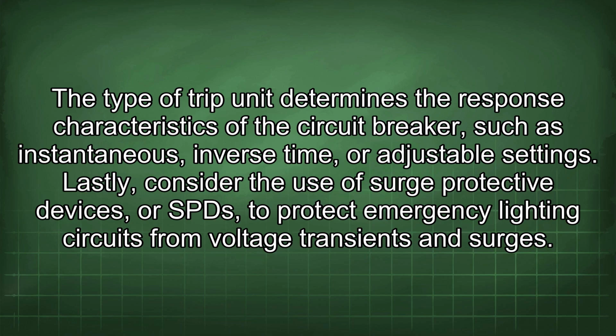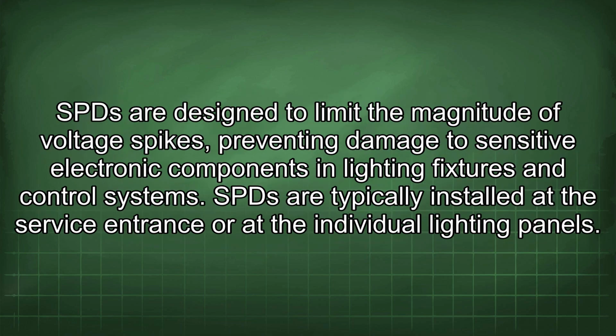Lastly, consider the use of surge protective devices, or SPDs, to protect emergency lighting circuits from voltage transients and surges. SPDs are designed to limit the magnitude of voltage spikes, preventing damage to sensitive electronic components in lighting fixtures and control systems. SPDs are typically installed at the service entrance or at the individual lighting panels.